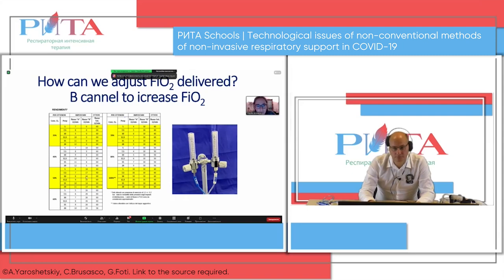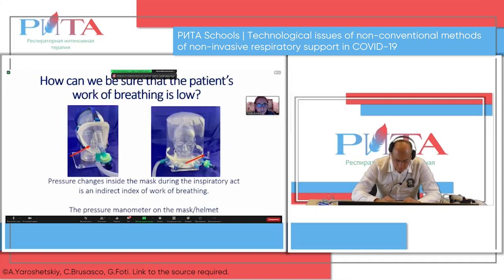Look at the table and put 16 in the B line. You should not put 8 in the A line. Why? A is the oxygen source to get 60 liters per minute. The table obviously has to give you the amount of oxygen from the source in the A channel to achieve 60, that's the minimum. But it might not be enough for your patient. So my suggestion is not to set up the A channel using this table, but to use the manometer column instead. Put the interface on in a way that you are sure you will not have leakages. Then set up the PEEP using the PEEP valve, and at this point you look at your column.